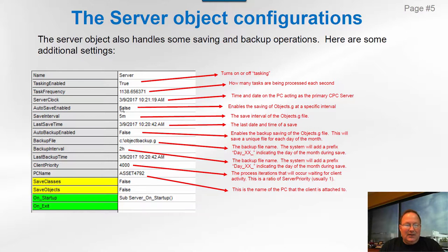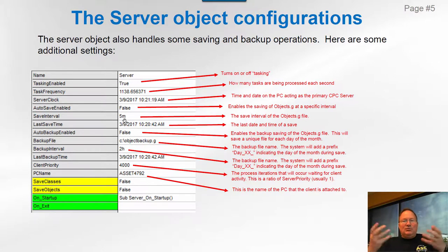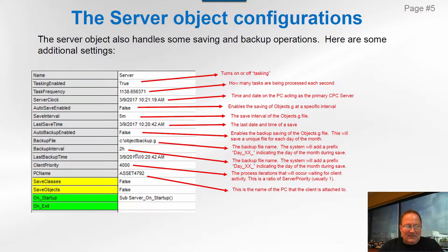Auto save enabled basically tells the server to save the objects.g file at a certain time interval — normally set for one minute or 30 seconds. It represents a snapshot in time of the current process. This is how we handle automatic restarts after power losses: the computer saves the objects.g file every minute, and when it boots back up, it loads exactly the configuration and real-time process state from the last save. Last save time is displayed here.